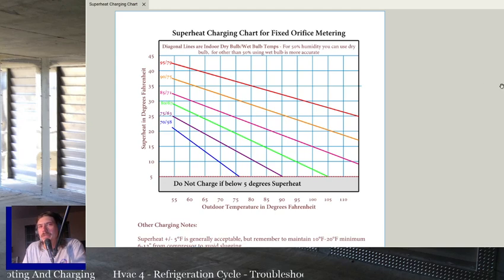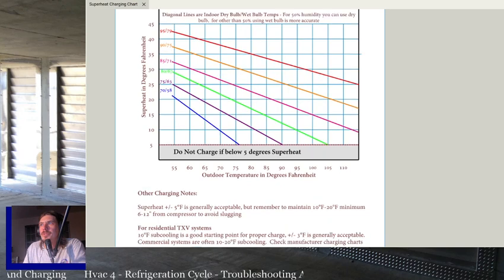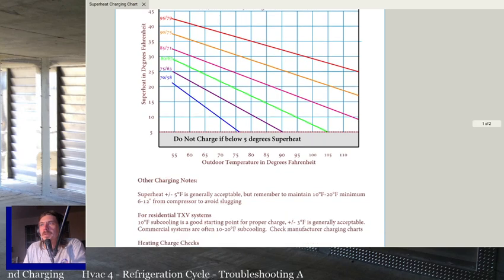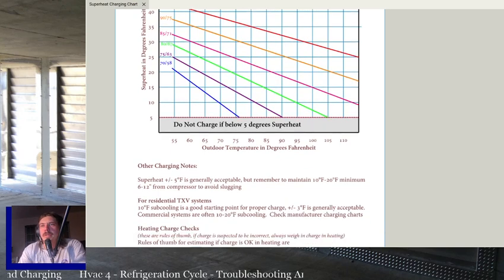Fixed orifices obviously are becoming less common, but they're still around. You still got to work on them. So when you run into them, this is usually what I use if I don't have their chart available. Remember, the closer you are to design conditions, the easier it is to get a good charge in. The more normal all those numbers are going to work. But sometimes you're charging when it's hot. Happens. All right. Superheat. Other charging notes.